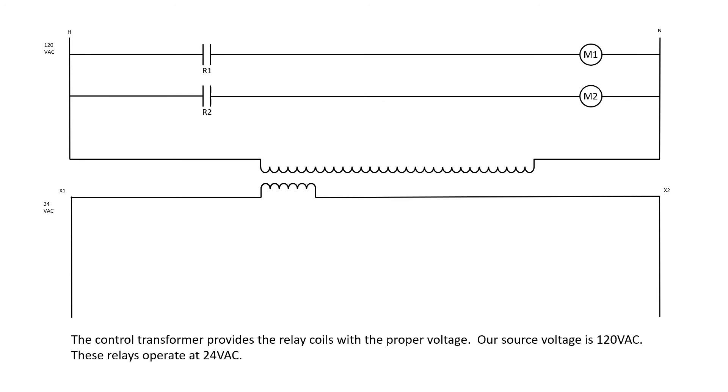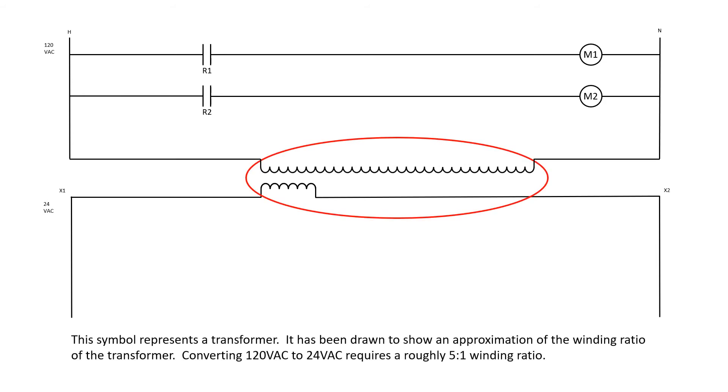Our source voltage is 120 volts. These relays operate at 24 volts. This symbol represents a transformer. It has been drawn to show an approximation of the winding ratio of the transformer. Converting 120 volts to 24 volts requires a roughly 5 to 1 winding ratio.